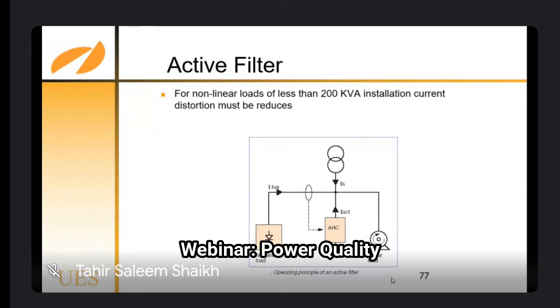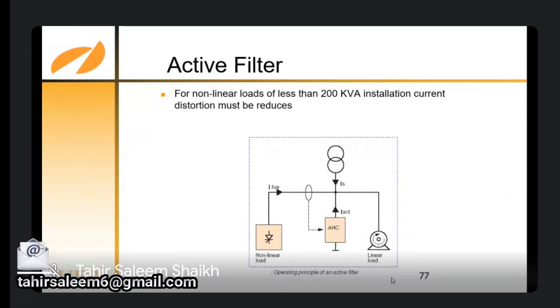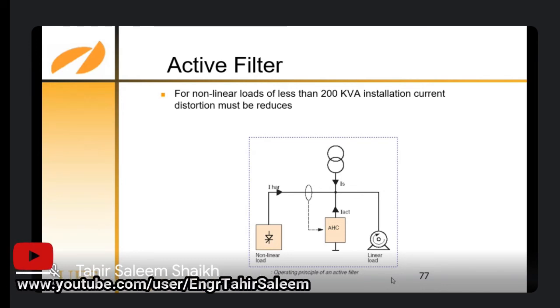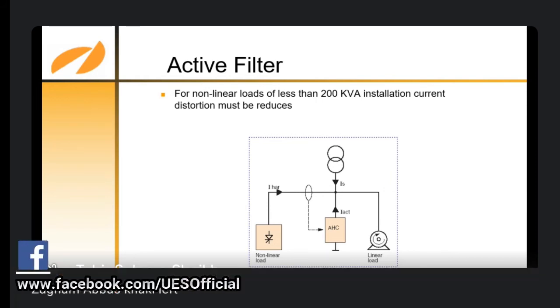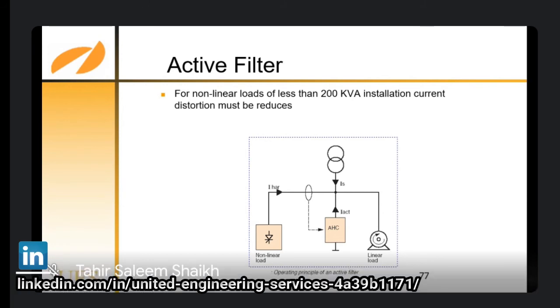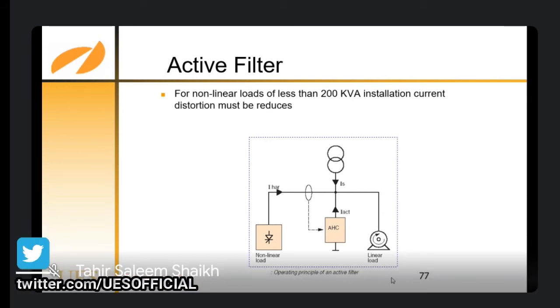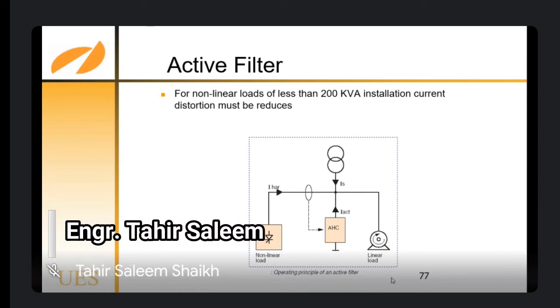this is the phenomenon: they put a sensor on the non-linear load, and this harmonic generator, the AHC, generates a harmonic opposite in phase to the harmonics generated by the non-linear load. So they nullify each other, being opposite to each other, and the harmonics are destroyed in this way. This is called an active filter.